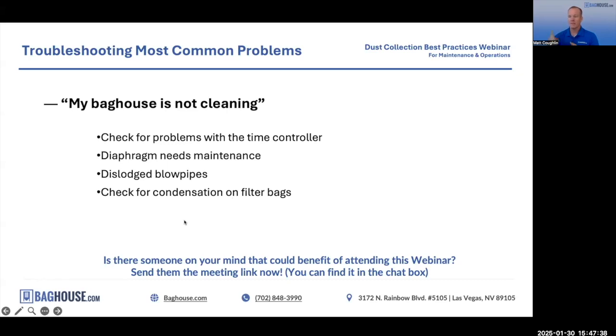So, okay, a couple items. You got your timer board, your pulse valves, your solenoids, the electrical connections, and your compressed air. So make a little checklist, go out there and check each one of those. One of those is your problem. If it's not, you have wet bags, then you should address that. But really, these systems are fairly simple once you understand the fundamentals, and that's where typically we'll find the problem.